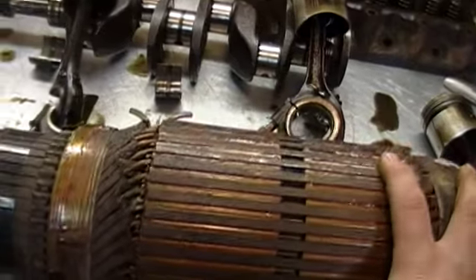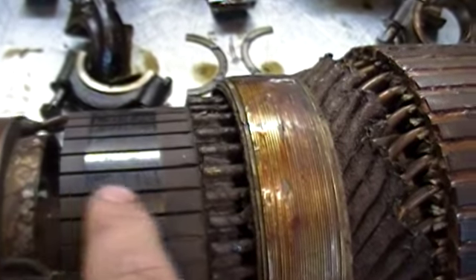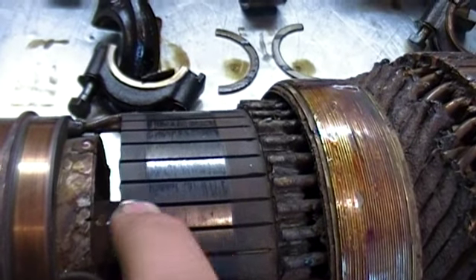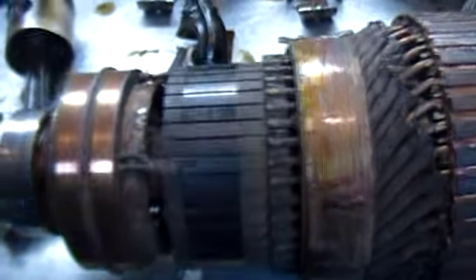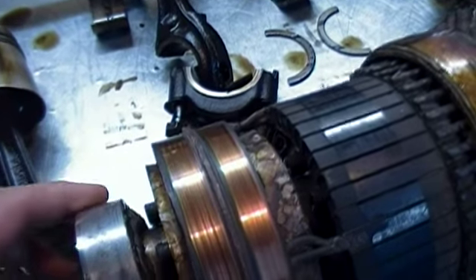It's a 75 pound hunk of steel and copper. The plates don't feel terribly worn out — I can definitely feel that the worn area is lower than the unworn area, but that could just be oxidation buildup. The AC side is nice and smooth all the way around.